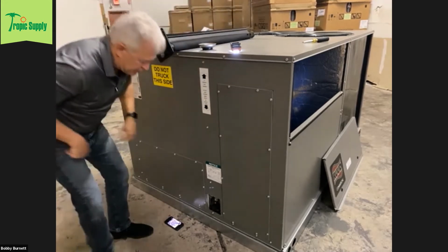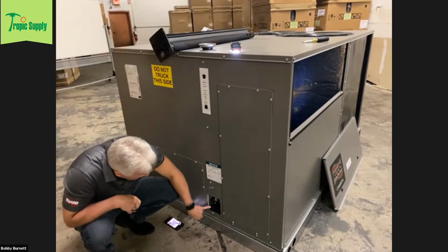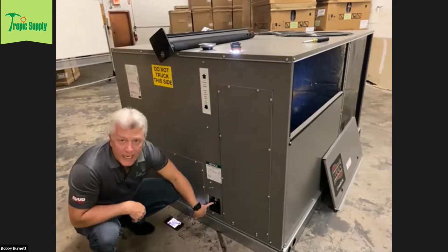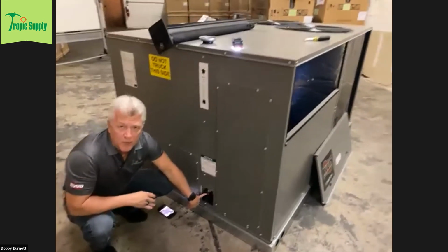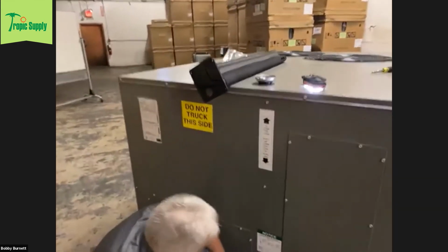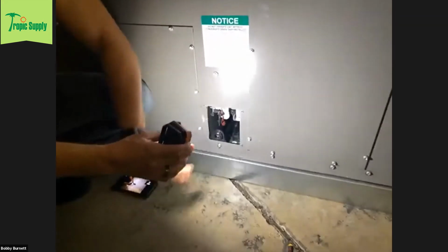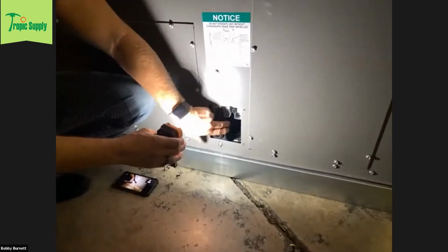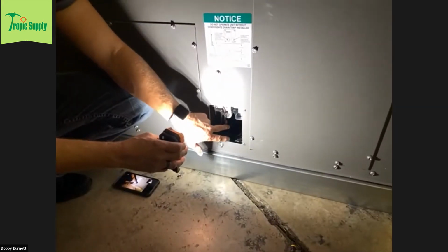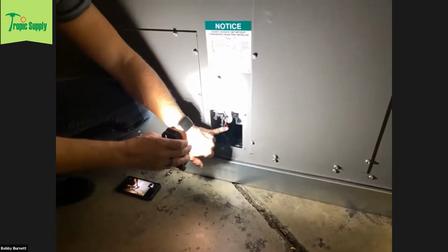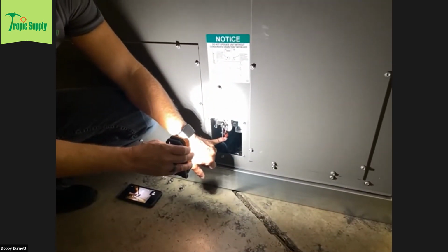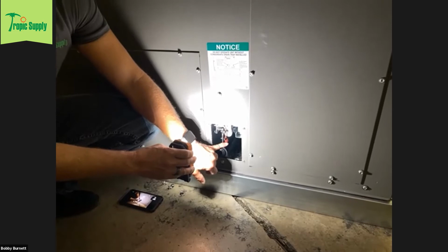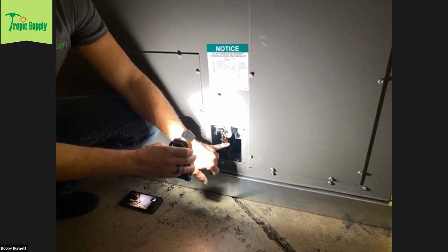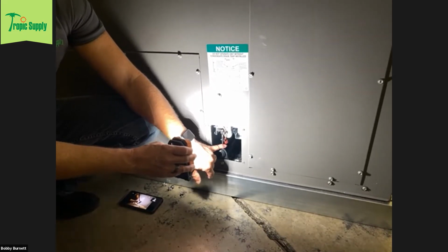One of the other features that I wanted to point out is, if you look in here, there's a little spade connector right here. That's a built-in float switch. So on this unit here, right here, when that pan slides in, this is sitting down right at the pan. So if water comes up and touches that, it activates the float switch and will shut the unit down. So you don't need a third-party float switch for this unit.